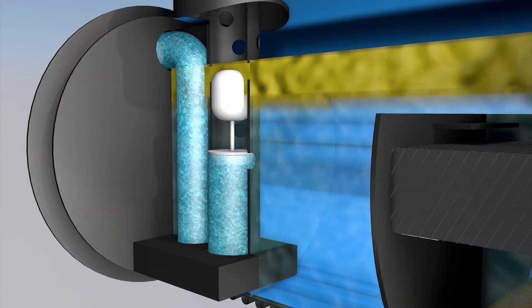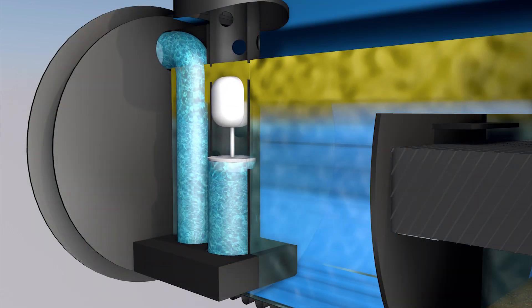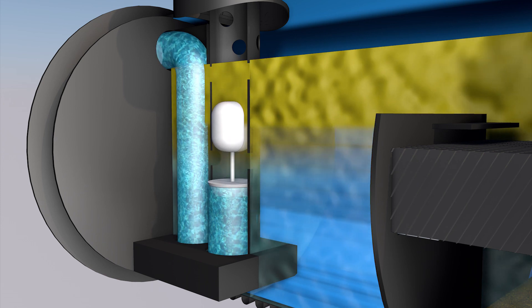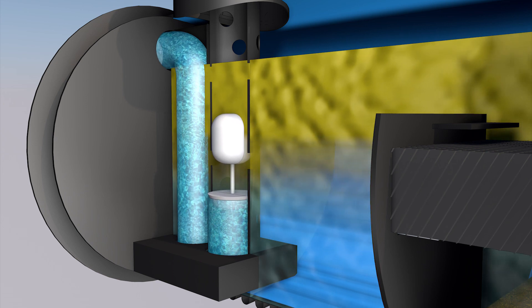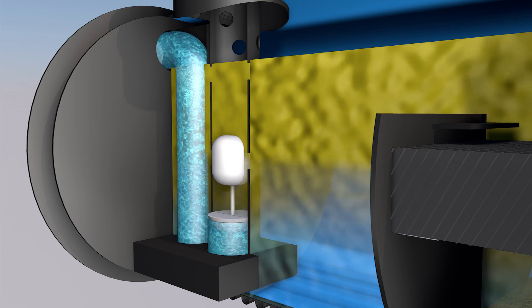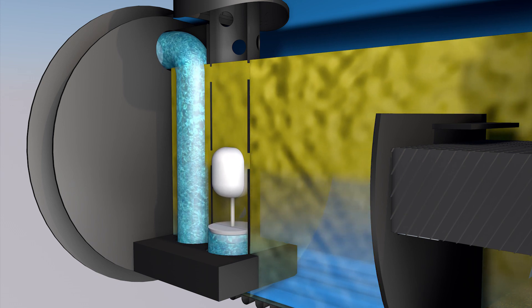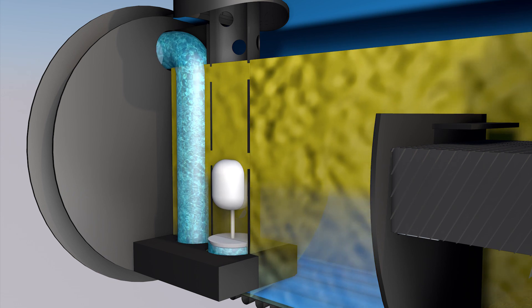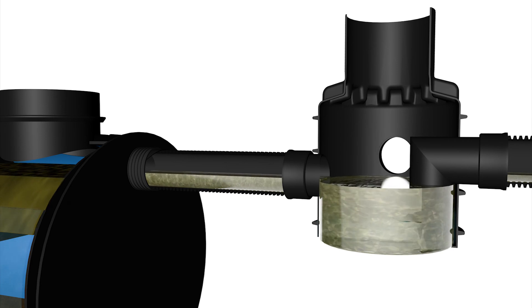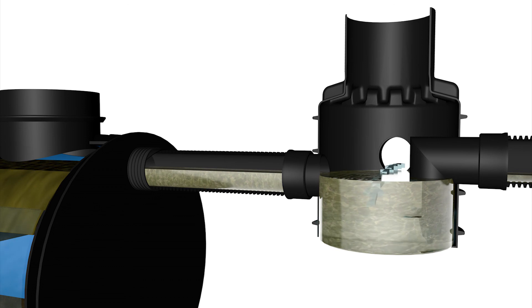In the final part of the standard tank, water travels from the bottom to the top as it crosses a lamellas filter for additional filtration. To exit the tank, liquids enter a vertical cylinder with large holes connected to a flow-returning pipe that leads outside the tank. This vertical cylinder has a floating shutdown valve designed to float on water but not on light liquids. In case of a light liquids spill inside the tunnel, they will reach the tank and settle on the surface. As the thickness of the light liquids layer increases, the floating height of the shutdown valve decreases inside the water exit cylinder, until the light liquids layer no longer allows filtered water to exit.